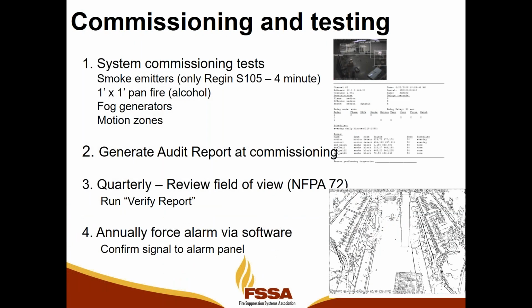Now, when the system is commissioned, we like to use a 4-minute smoke emitter if possible. Fog generators can be used. We recommend alcohol be used because it's a clean fire if possible, or motion zones just to show that the analytics are working. Once the system is commissioned and the settings are set, we generate an audit report. At 6 months, we run a verify routine in the software to confirm that the settings are the same as commissioning.